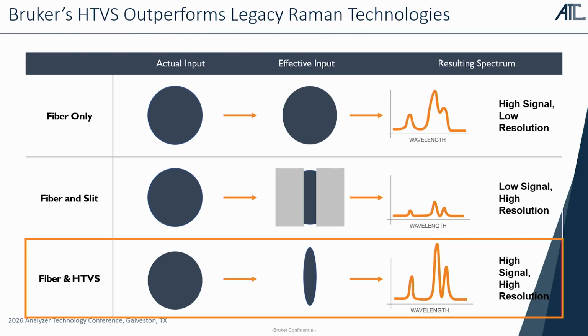When we talk about this slit and the purpose of the slit, we really want to be able to resolve peaks, because one of the main benefits of Raman spectroscopy is the selectivity, right? But sensitivity has always suffered as a result, because that slit blocks so much of the light. So what we've done is rearrange the light into the shape of a slit, and now we get the best of both worlds. That is what allows us to do things like wastewater management and really low ppm detection limits. Raman was always great with selectivity, but it suffered in sensitivity. And now we have a new way.